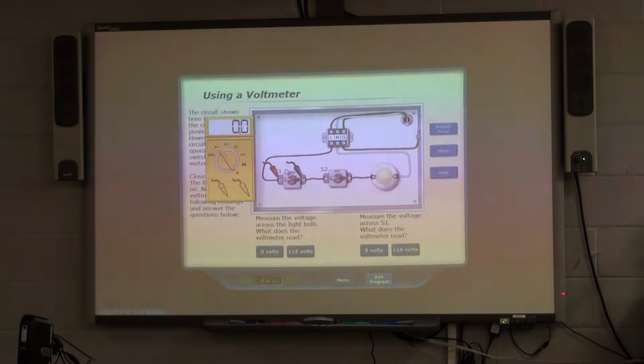All right, now, if we go back and reference neutral or ground, go to neutral. What are we going to read on the other side of this one? 0? No, you're going to get about 110. So we get it all the way down to the load, right? Yeah, that's when it stops. But here, we're at the same position. All right, so very good.